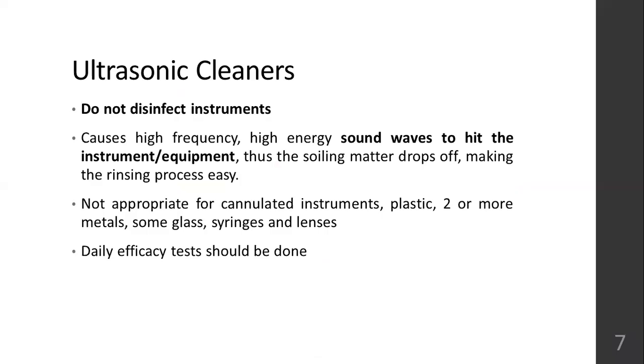Then you have ultrasonic cleaners. These cleaners don't disinfect the instruments, but they create high frequency, high energy sound waves, and because of the sound waves, whatever is attached to the equipment, dirt, soiling, tissues, will drop off. This makes the rinsing process very easy. Sometimes when you rinse with water and detergent, it's not enough. In that case, ultrasonic cleaners are used so that whatever is stuck falls off from the instrument. They don't disinfect, they just make sure the soiling detaches.